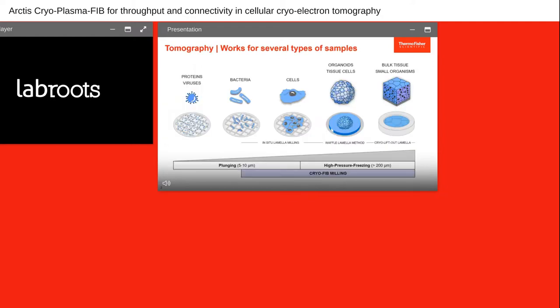Tomography can be done on a range of different sample types with different thicknesses. Protein and virus particles can be plunge-frozen and do not require thinning — they are thin enough to directly image in the transmission electron microscope. But for more complex samples, from bacterial cells to eukaryotic cells, or larger objects like tissue, small organoids, or small organisms, some form of thinning is required to make the sample accessible for transmission electron microscopy. That is why the cryo-FIB milling technique and the Arctis system are so important for this essential step of sample preparation.